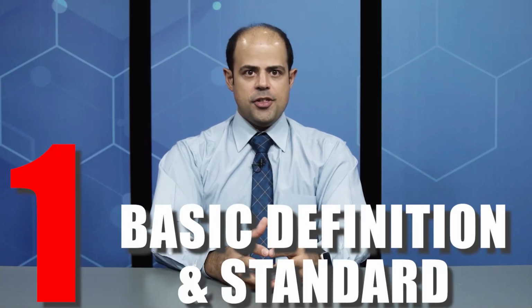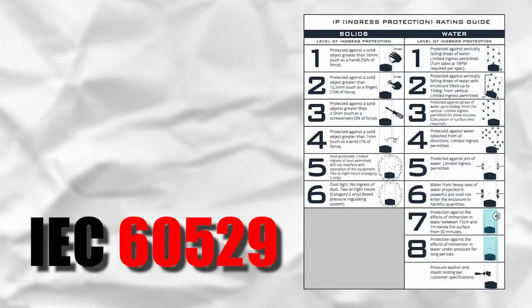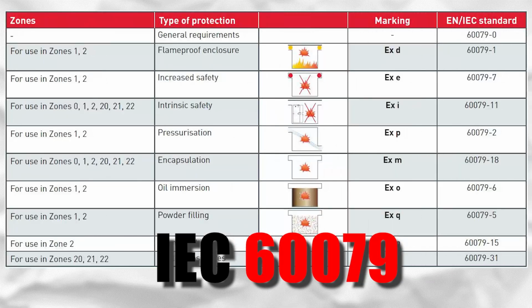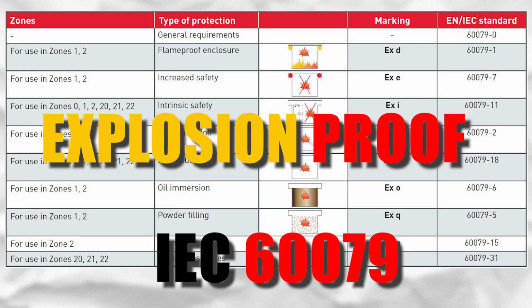As the first step, I'm going to start with basic definitions and standards. As you may know, for designing and selecting a suitable instrument, we need to follow a reference called a standard. There are a lot of standards published in the world, and we can apply them to design and choose the device. An example could clarify this issue. IEC 60529 is applied to choose the ingress protection grade, or IEC 60079 is used to design the suitable explosion-proof type according to hazardous area classification of the industrial plant.